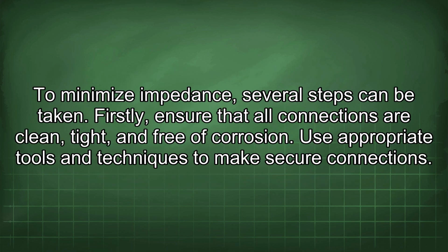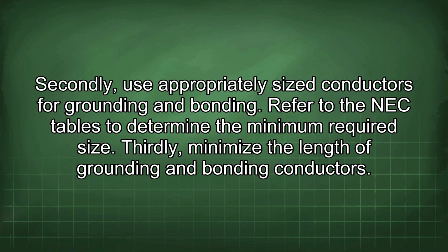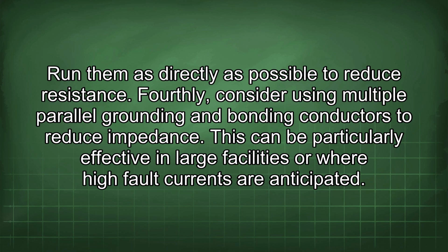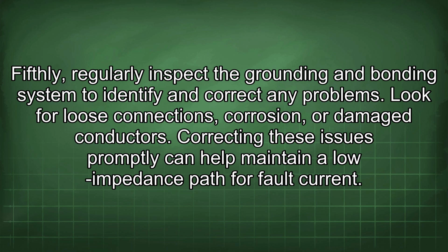To minimize impedance, several steps can be taken. Firstly, ensure that all connections are clean, tight, and free of corrosion. Use appropriate tools and techniques to make secure connections. Secondly, use appropriately sized conductors for grounding and bonding. Refer to the NEC tables to determine the minimum required size. Thirdly, minimize the length of grounding and bonding conductors. Run them as directly as possible to reduce resistance. Fourthly, consider using multiple parallel grounding and bonding conductors to reduce impedance. This can be particularly effective in large facilities or where high fault currents are anticipated. Fifthly, regularly inspect the grounding and bonding system to identify and correct any problems. Look for loose connections, corrosion, or damaged conductors. Correcting these issues promptly can help maintain a low impedance path for fault current.